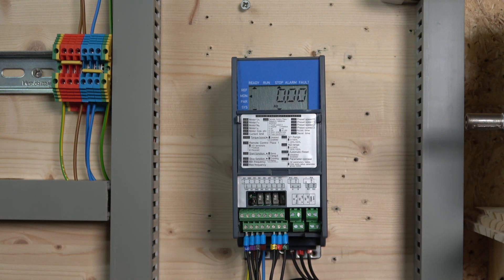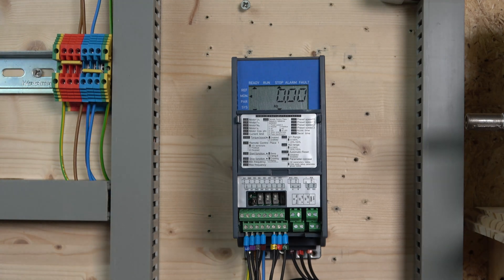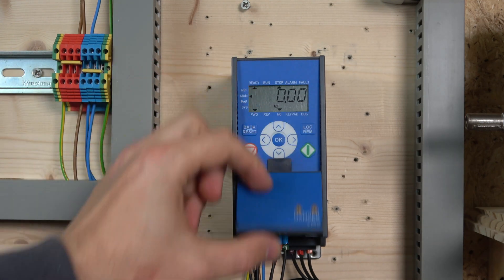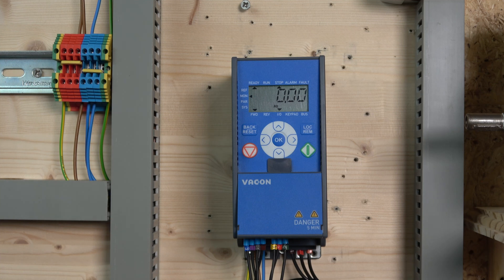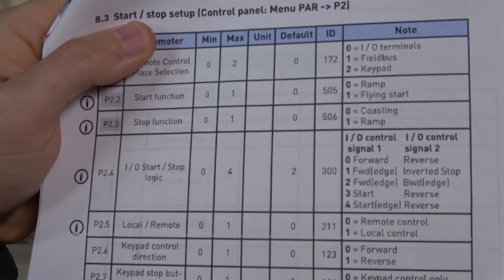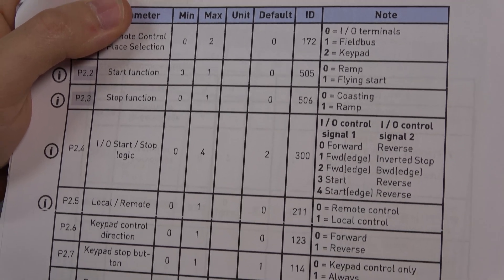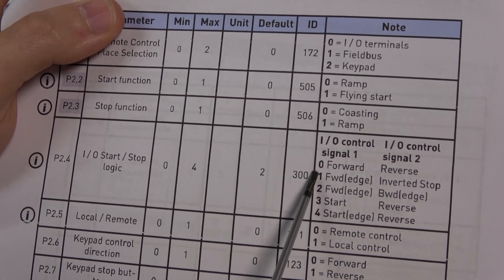Once you've done the wiring, we need to adjust how the digital inputs are configured. Go to I/O configuration in parameter 2.4 - I/O start stop logic. It shows signal one (digital input 1) and signal two (digital input 2). We're going to change it to 1, which is forward edge and inverted stop.